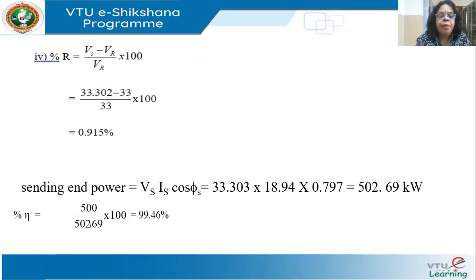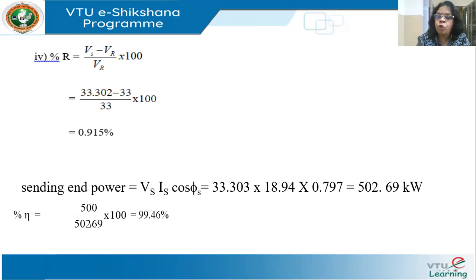The percentage voltage regulation is (VS − VR) / VR × 100 = (33.302 − 33) / 33 = 0.915%. This is excellent regulation. For short lines, because line length and voltage drop are less, the regulation will be very good.